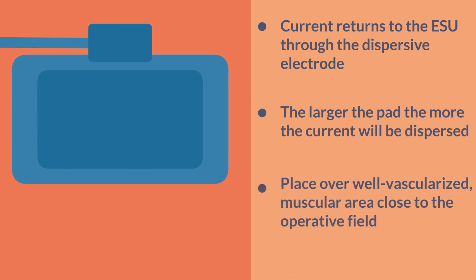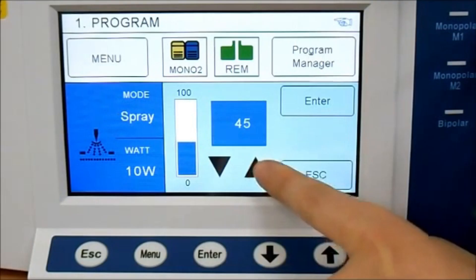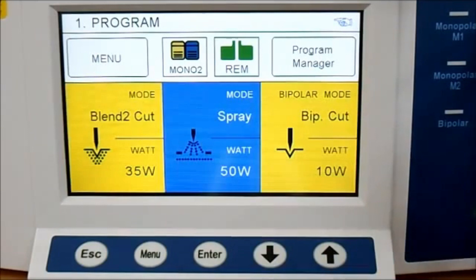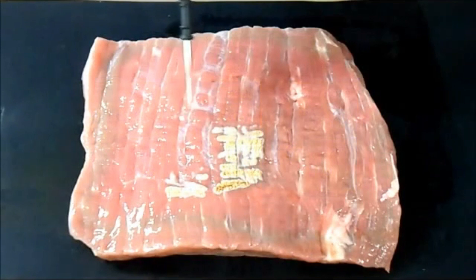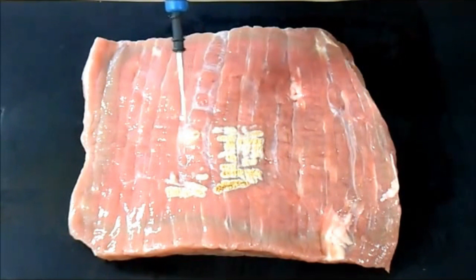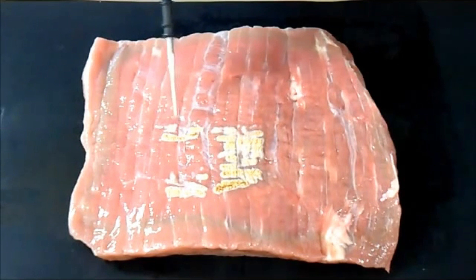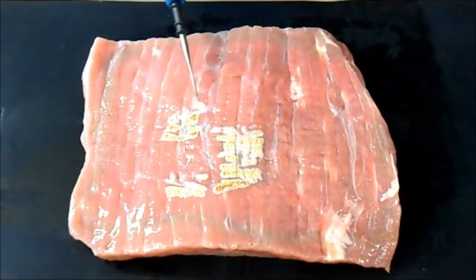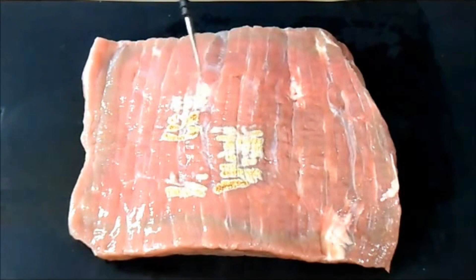The third mode is fulguration mode in electrosurgery. In fulguration mode, the electrode is held away from the tissue so that when the air gap between the electrode and the tissue is ionized, an electric arc discharge develops. In this approach, the burning to the tissue is more superficial because the current is spread over a tissue area larger than the tip of the electrode. Superficial skin charring or carbonization is seen over a wider area than when operating in contact with the probe, and this technique is therefore used for very superficial or protrusive lesions such as skin tags. Ionization of an air gap requires voltage in the kilovolt range.